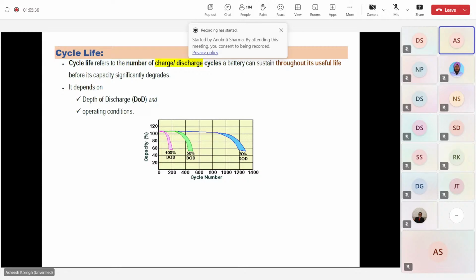If you look at this diagram, it clearly shows that if you are using a battery with 100% DOD from its capacity, this is going to result in the least number of cycles, around 200. If you are using it with 50% DOD, these cycles are going to be around 500. And if you are using it with some 30% DOD, these cycles are going to exceed more than 1200, and definitely this is going to give you a longer life.